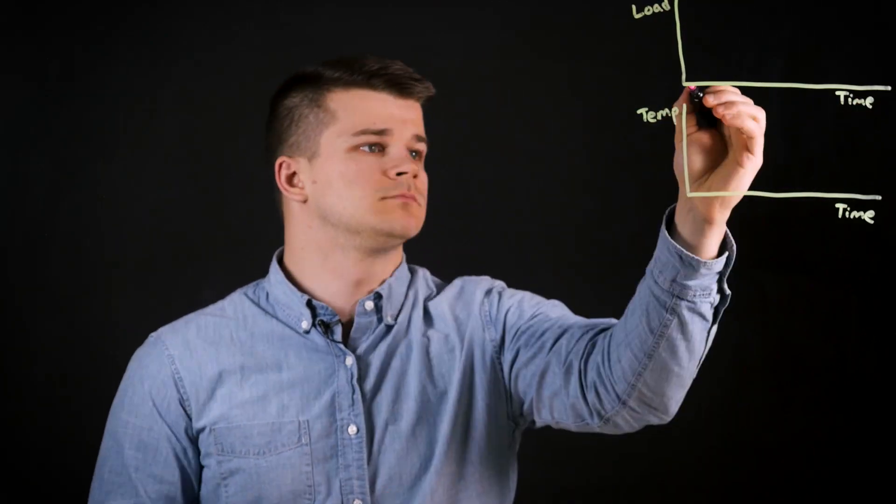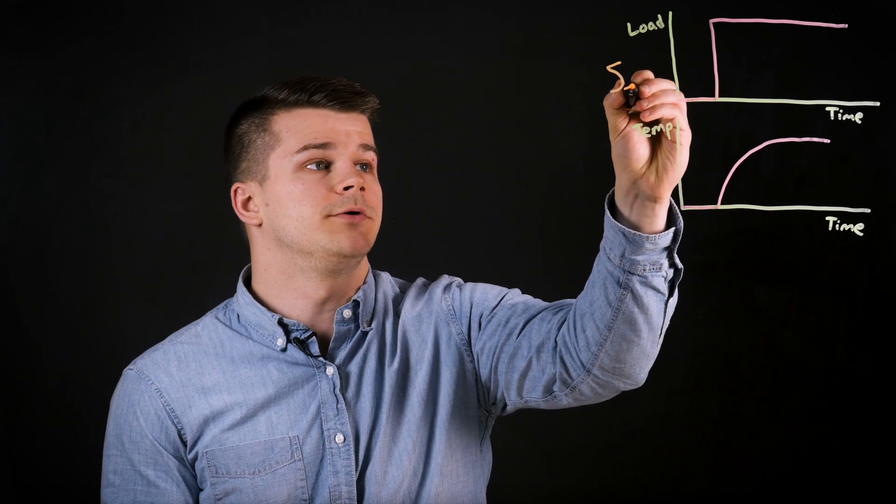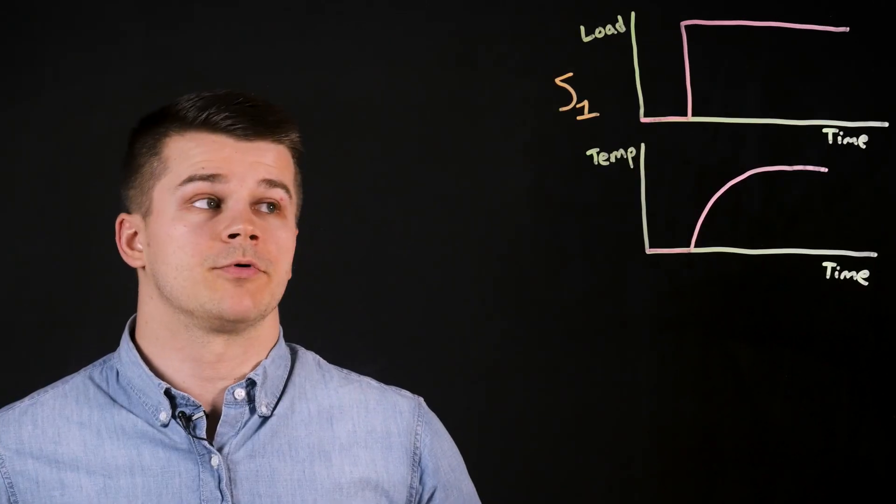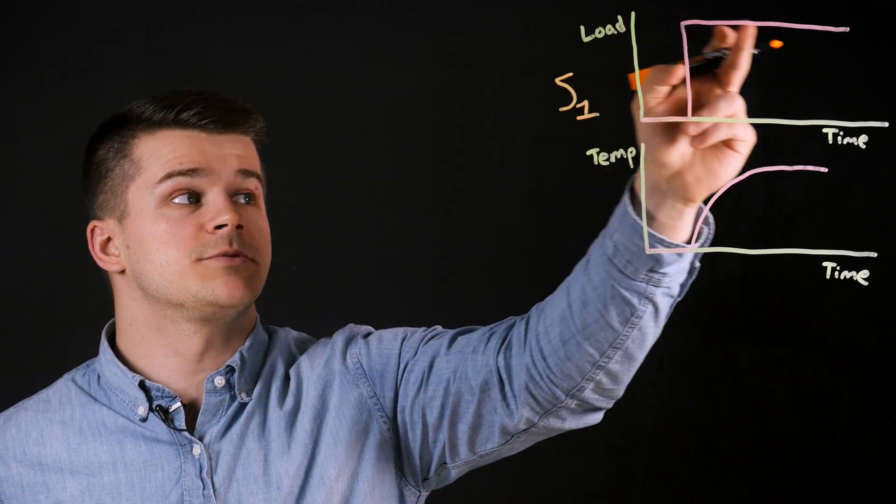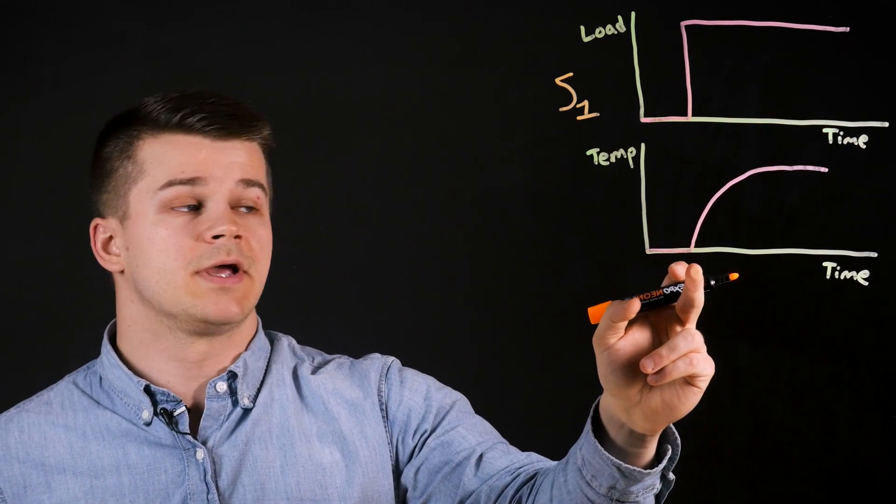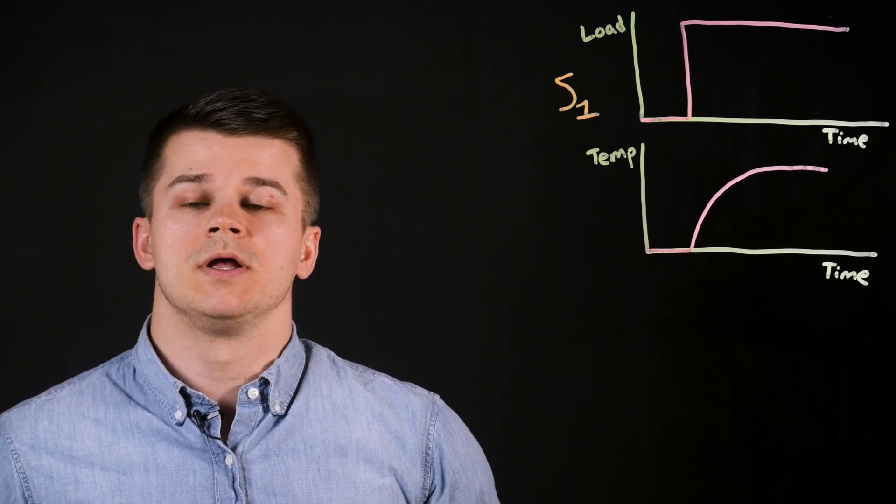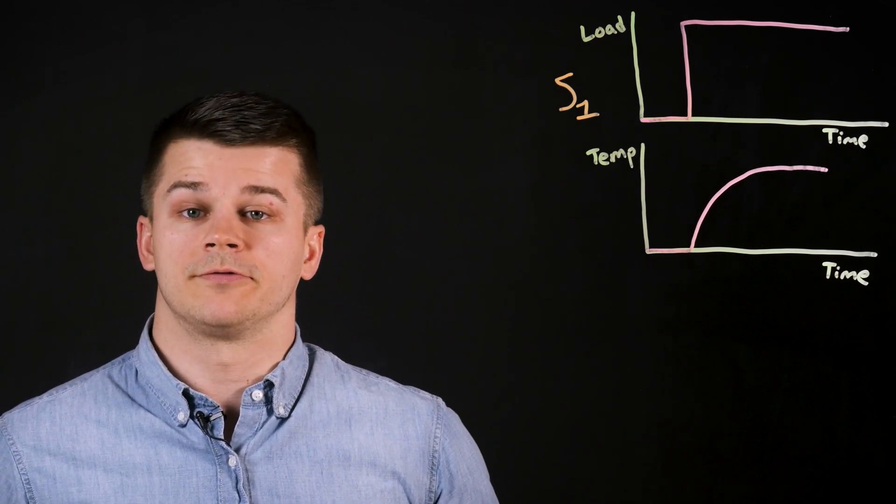The first motor duty cycle we'll talk about is continuous duty, also referred to as S1 duty. In this type of operation, a constant load is applied throughout the operation, and the temperature goes from ambient and is allowed to reach a constant temperature at the motor's thermal equilibrium. This is the simplest type of motor duty cycle.